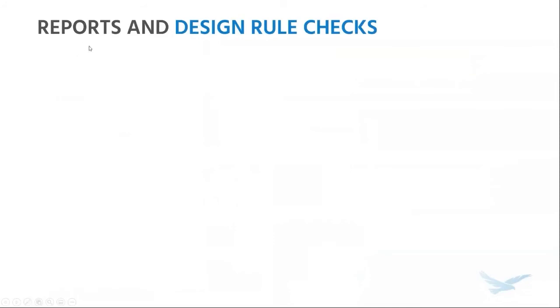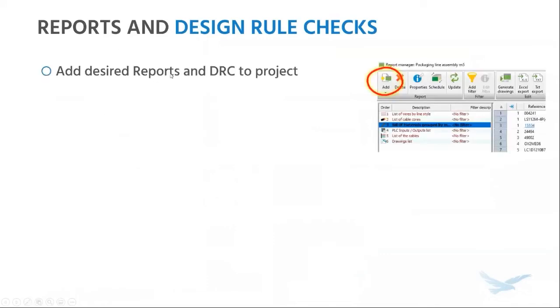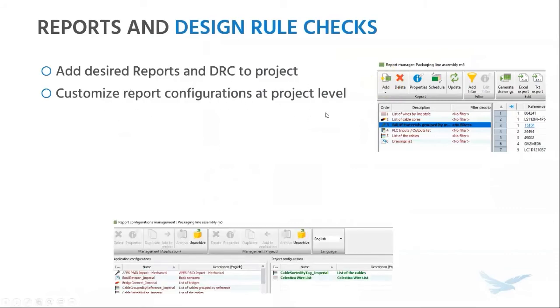I've got a quick section on reports and design rule checks. If you would like all your new projects to have specific design rule checks and reports, go ahead and add them in — things like a bill of materials, wire from-to list, a drawing list, list of cables. Things that all projects should have — why not just add it to the template. You also have the option of customizing these reports at a project level, so they remain unaffected at the application level if they're being used in other projects. Something to keep in mind: these reports are linked to the unit system. If you are in a metric project, you have access to metric reports; if you're in an imperial project, you access imperial reports. Pretty much all the default reports in SolidWorks Electrical come in both flavors.